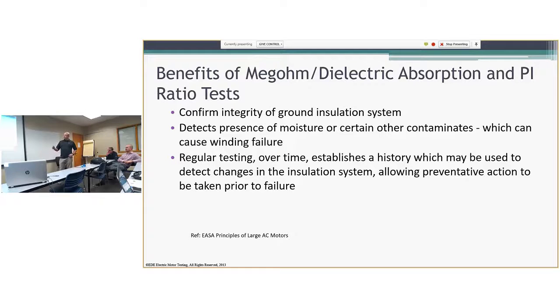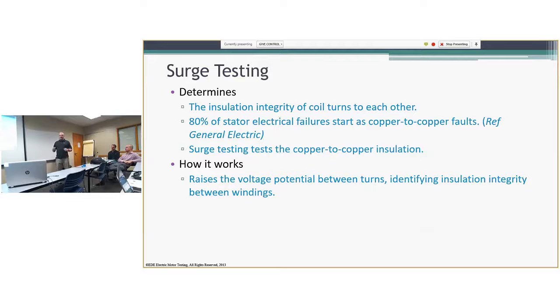Surge testing tests insulation integrity of the coil turns to one another. So actually turn to turn, phase to phase type problems. And that's, once again, usually when the insulation on the wires starts getting thin from all that movement that you saw. Or sometimes things can get in the motor and nick or damage it.